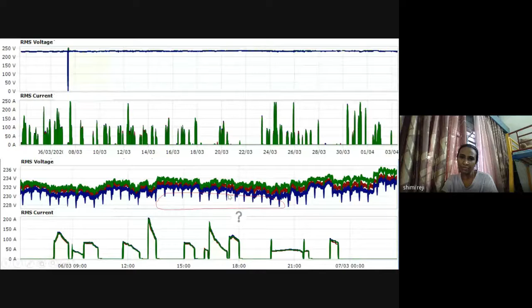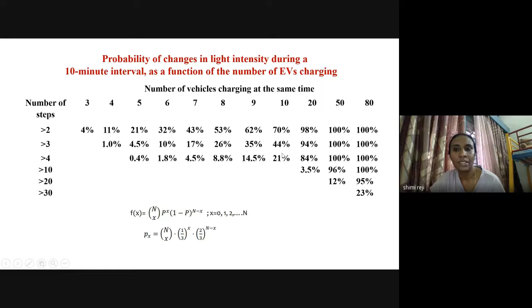PST is calculated for a 10-minute interval, so in a 10-minute interval, what is the probability of getting 1 dip? That is 1/3. Based on this probability, we took a real network and assumed around 50 cars charging at the same time, and studied what is the possibility of getting more than 4 dips. When 50 cars are simultaneously charging, there is 100% probability of more than 4 dips, and 96% probability of more than 10 dips.